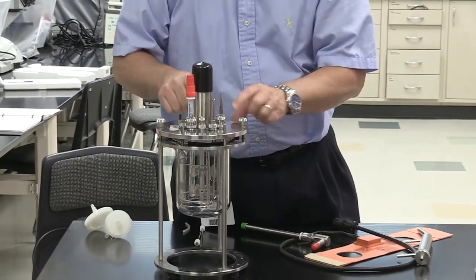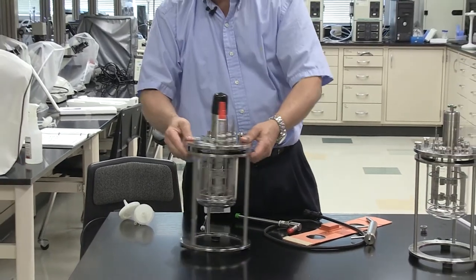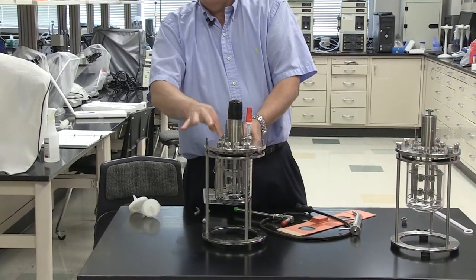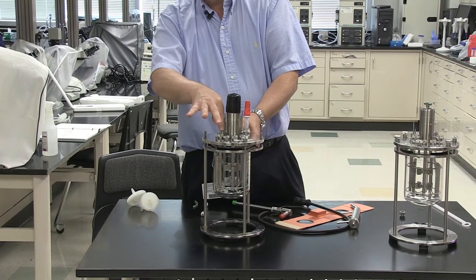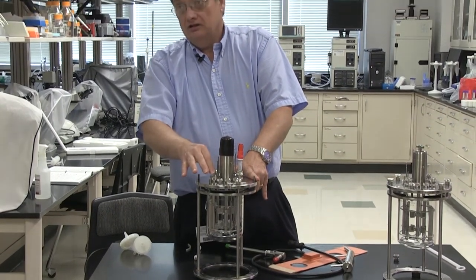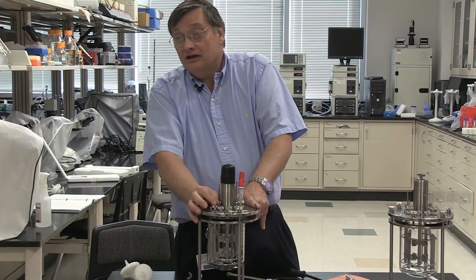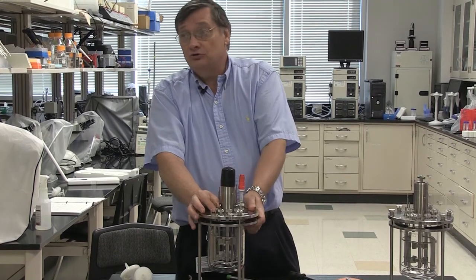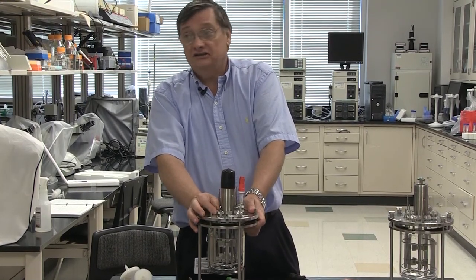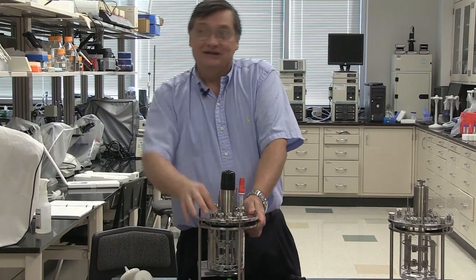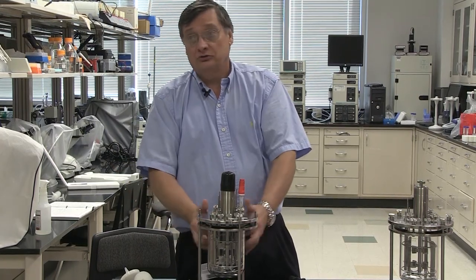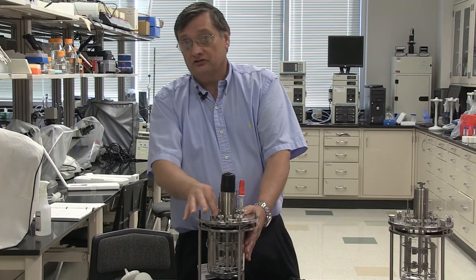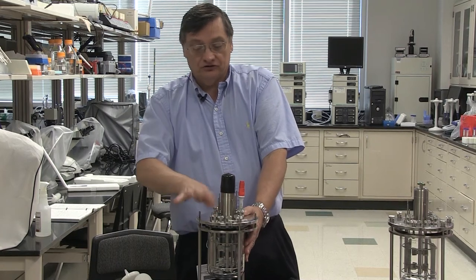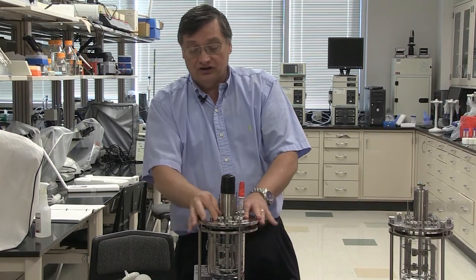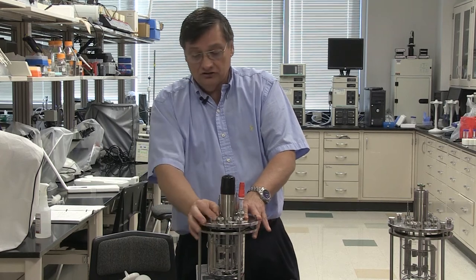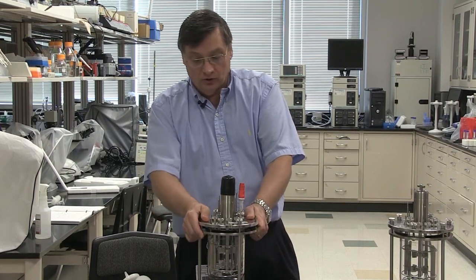Also, when you're assembling and putting the thermal well in, remember, here's the thermal well, you don't want it to be close to the cooling coil, because that would confuse it. It would always be cool and it would be putting in heat, ask for more cooling, it's still cool, ask for more heat, so you would overheat the vessel just because it was misreading the temperature. So just make sure your thermal well is not near the cooling coil.